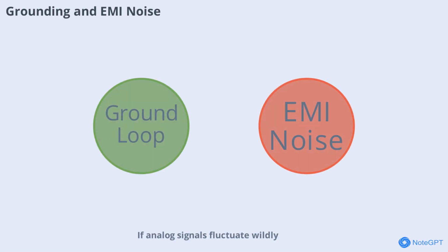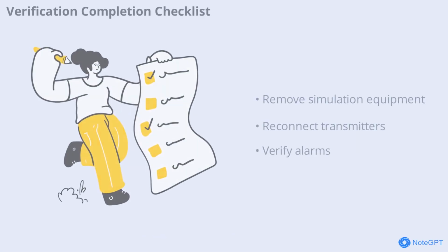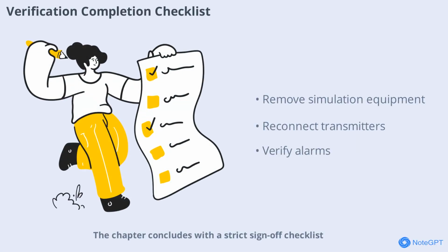If analog signals fluctuate wildly, there is likely a ground loop or electromagnetic interference (EMI) from power cables routed too close to signal cables. Proper grounding and cable routing are essential for stable signal transmission and system reliability. Addressing these issues prevents erratic behavior and ensures accurate measurements. The chapter concludes with a strict sign-off checklist to ensure everything is documented before functional testing begins. Key steps include removing all simulation equipment, reconnecting all transmitters, verifying all alarms, and ensuring no active forces remain in the PLC. This checklist guarantees that the system is ready for safe and reliable operation.